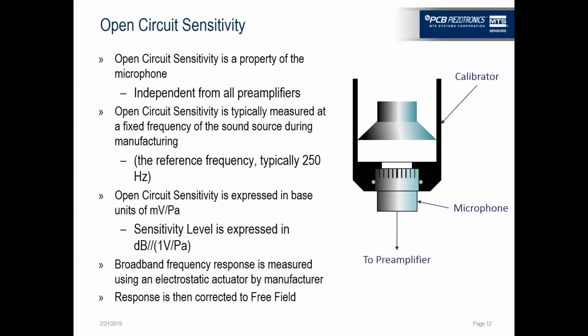As I said, open circuit sensitivity is a property of the microphone, independent from the preamplifier. If you're buying just a cartridge from us, it's measured typically at a single frequency, 250 hertz. We give it to you in millivolts per Pascal, and we'll also give you sensitivity level in dB, which is dB with reference to 1 volt per Pascal.